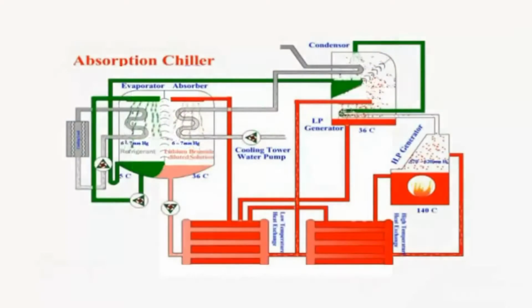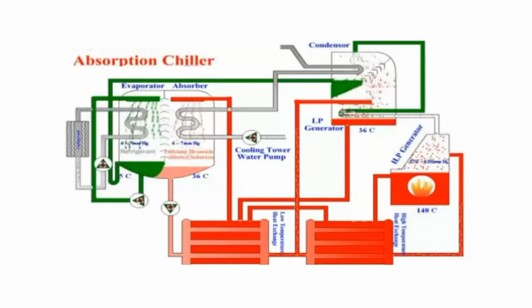The evaporated water will now travel to the absorber, where it is absorbed into an incoming spray of highly concentrated lithium bromide coming in from the generator. The now dilute absorbed solution circulates back to the generator.